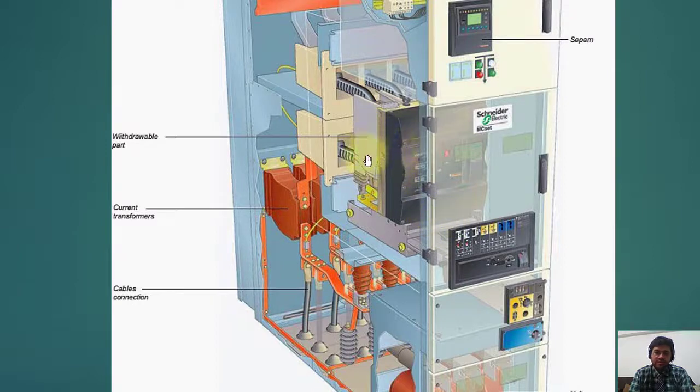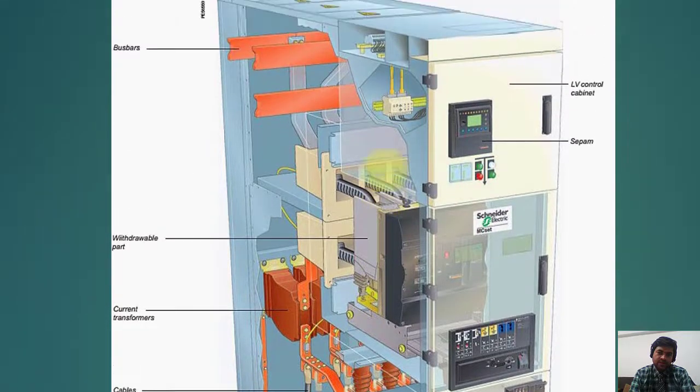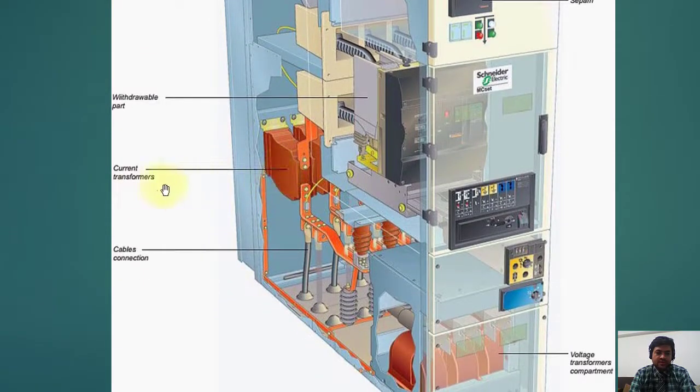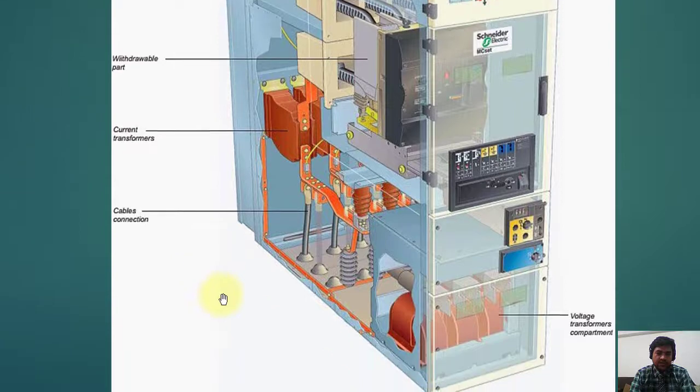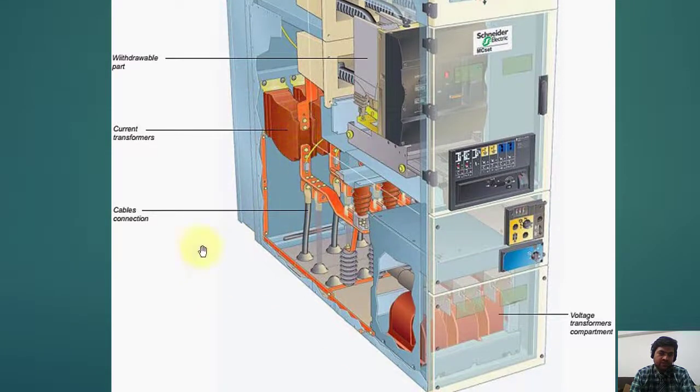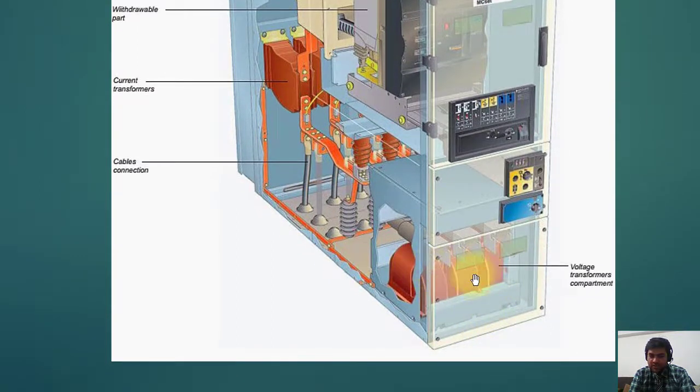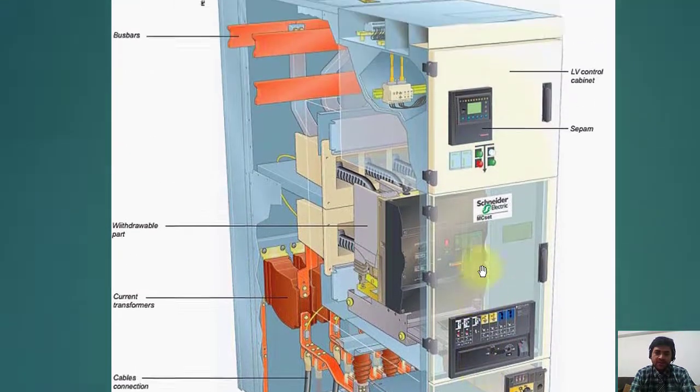Down there you can see this is the circuit breaker trolley. It can be racked out and racked in as I told you before. This is basically the bus power which is running between the panels, which is common between the panels. This is the current transformer installed in series of the circuit. These are cable connections which can be incoming and outgoing cables. This is the voltage transformer which is installed downside. This compartment, if you open it, you can access the voltage transformer. So this is how the MV panel looks like.